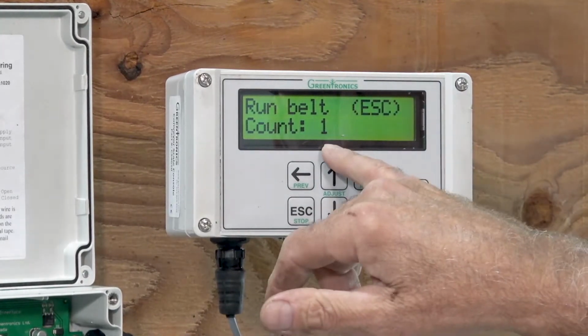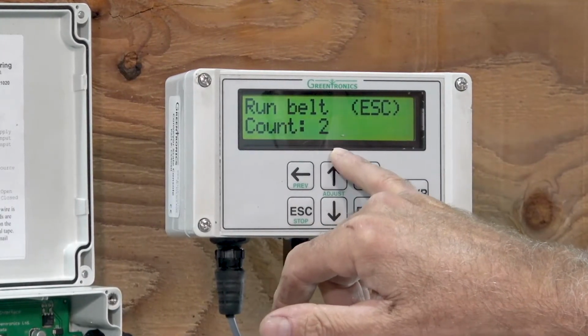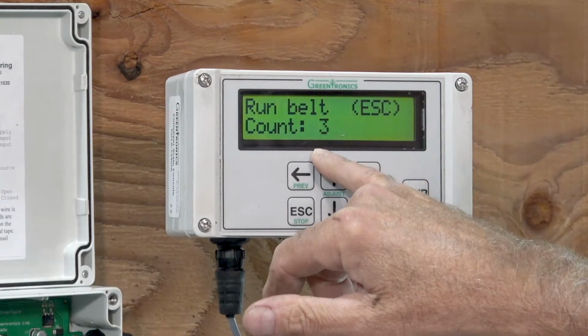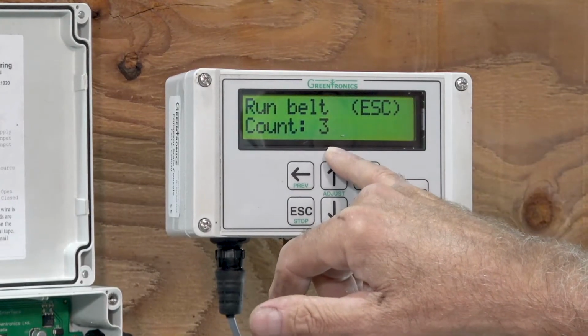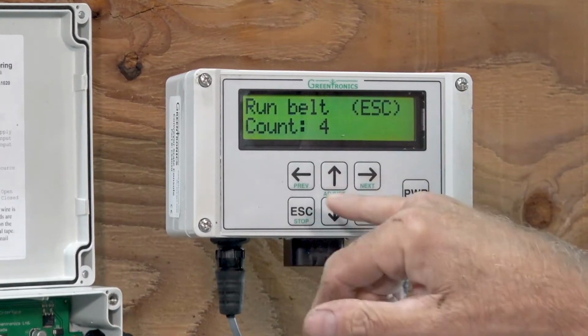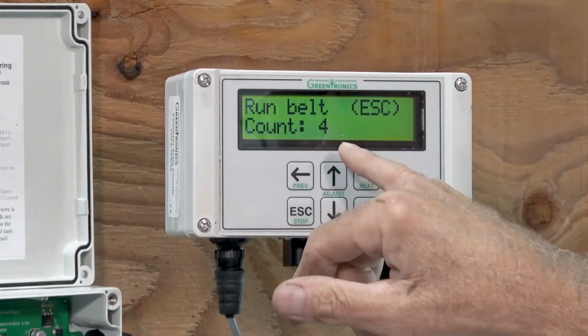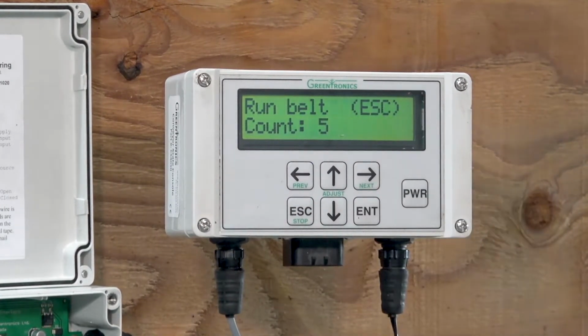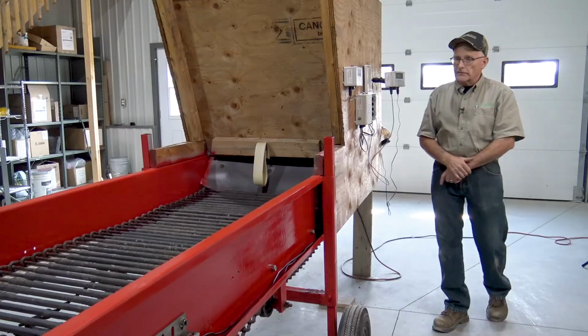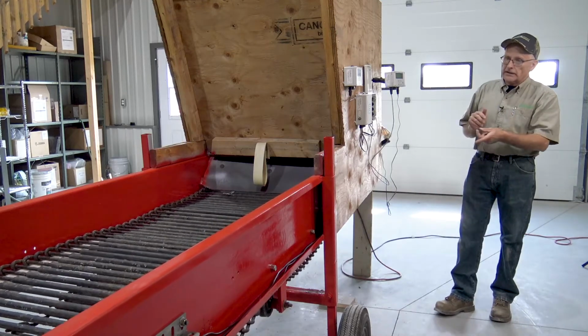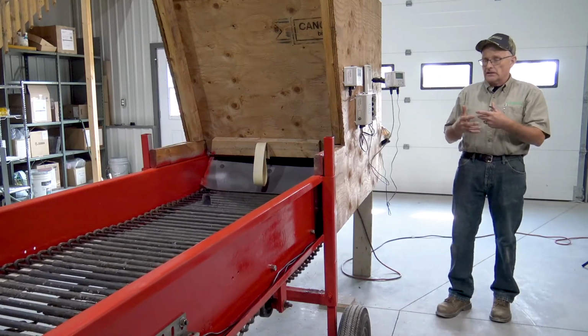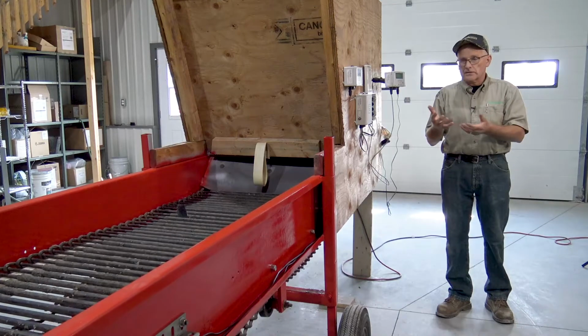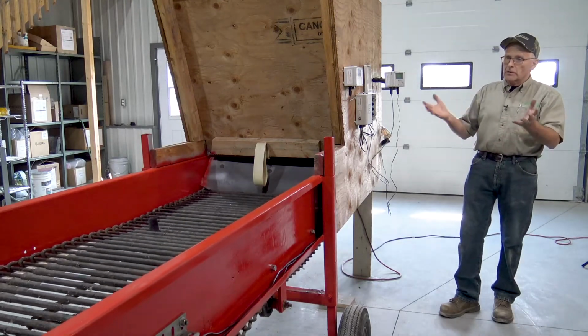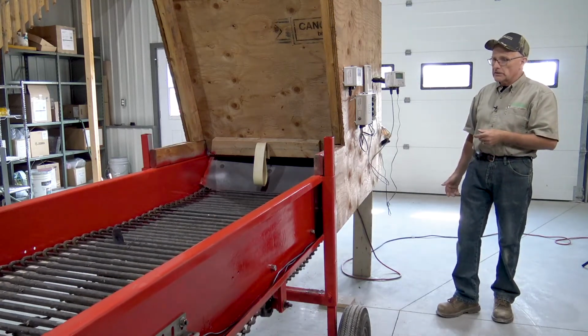Now you see this count. That's the magnet every time it passes the sensor. It takes a long time. The shaft turns slow, and there's also a slight delay in how it displays that. I like putting more than 1 revolution in a tare length calibration because it means that when we do the tare calibration, we're averaging over more than just 1 revolution.